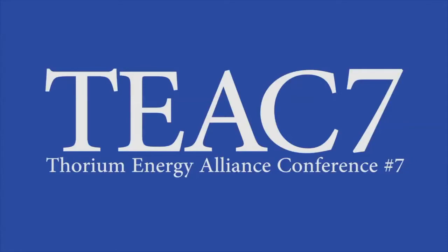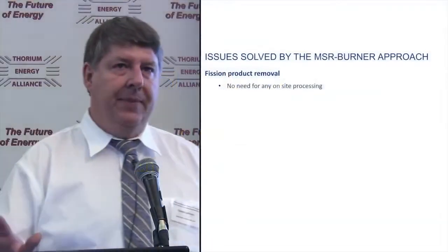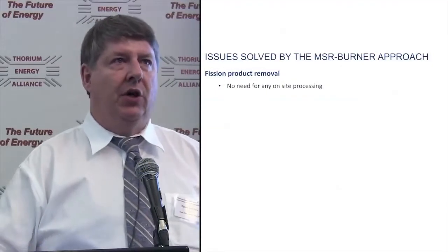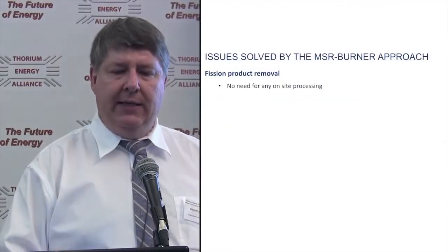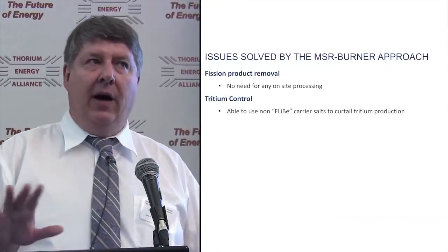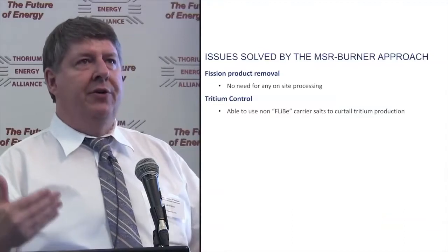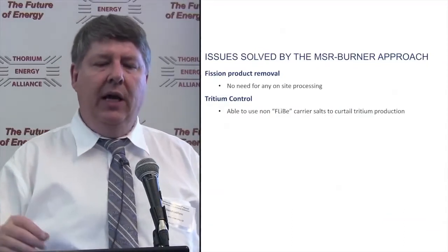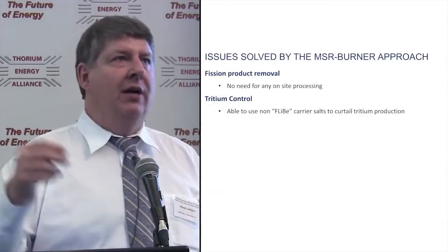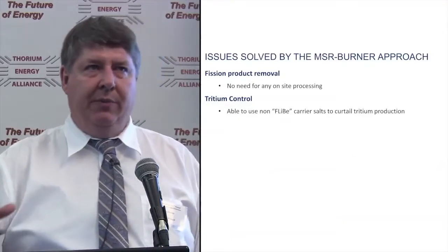Issues solved by going to the burner approach: fission product removal — we don't have any need for on-site processing. We may choose to process the salt once we finish it, but that's a nation's choice. Tritium control — we're not giving up on enriched lithium or beryllium, but when you're not a breeder and not trying to save every last neutron, we have the ability to use non-FLiBe carrier salts that really knock down tritium production by about 99%.